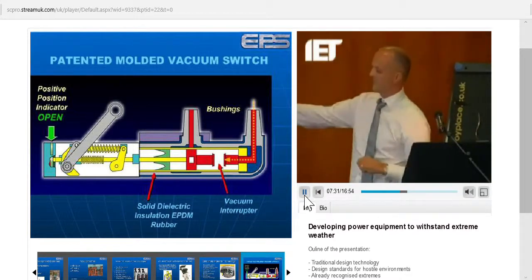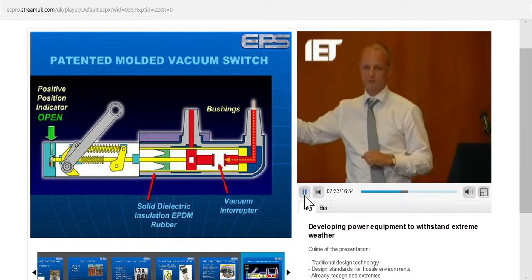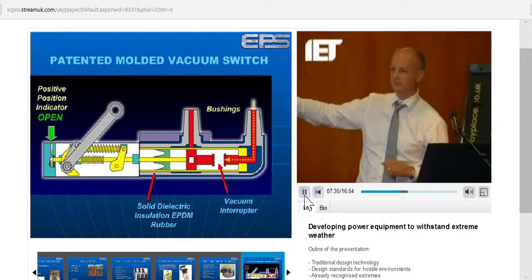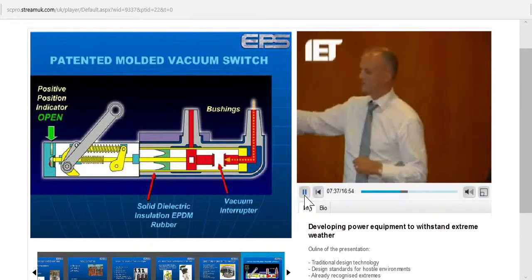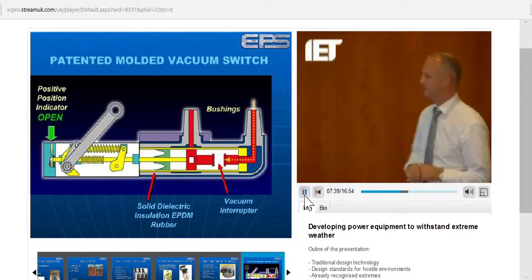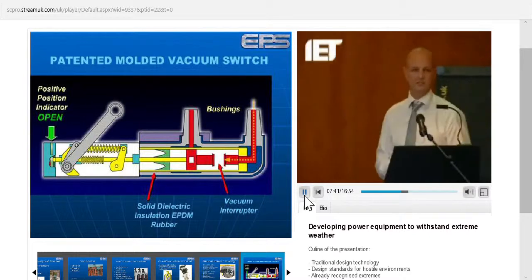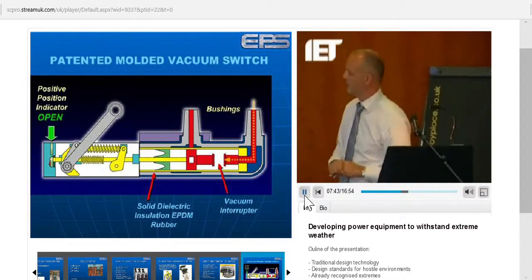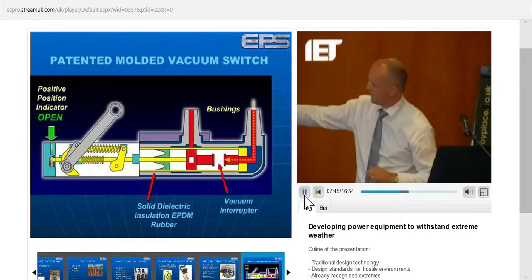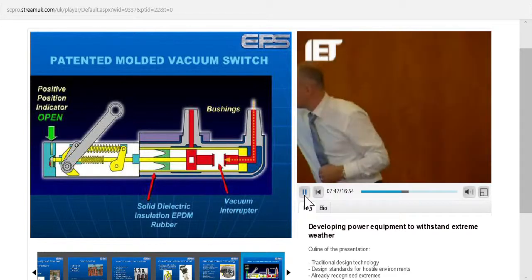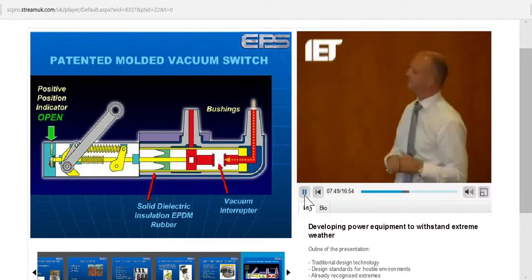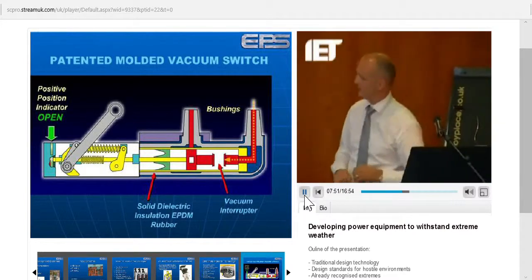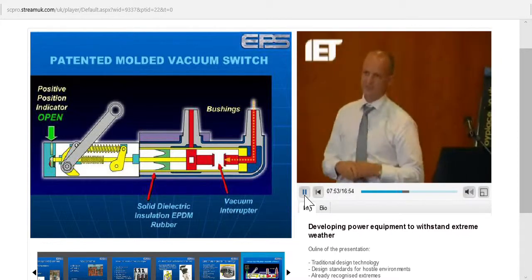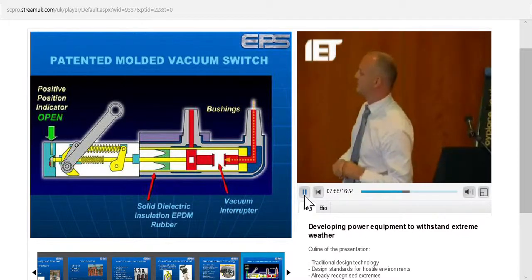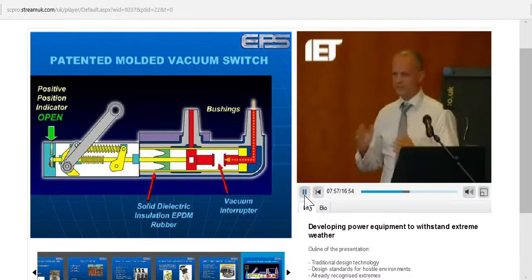On the right-hand side, this is conducting. So we've created a Faraday cage. In other words, there's no voltage across that air gap. On the left-hand side, of course, it's insulating. The blue structure on the outside of the switch is a conducting layer, and then we have a semiconductor going through to full insulation where the cable connectors are made to stress relieve that joint area there.